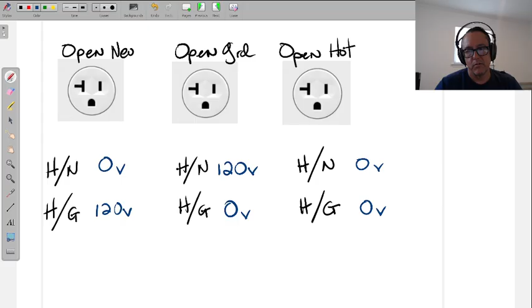All right, good so far. Now here's a fourth problem that could happen, and that is reverse. When things get reversed. Now, there are two ways that somebody can reverse things in a device. One of them is almost a non-issue, and that's when somebody reverses the hot and the ground. This is going to present a short circuit, either when you plug something in or when they mount it onto the box and turn the breaker on. If there's a ground and it's grounded and the ground is heading back to the panel and you have the ground on the hot side and you have the hot on the ground side, then it's going to short something out. Something will pop on the breaker. Or if it's a GFCI, it'll immediately just trip.